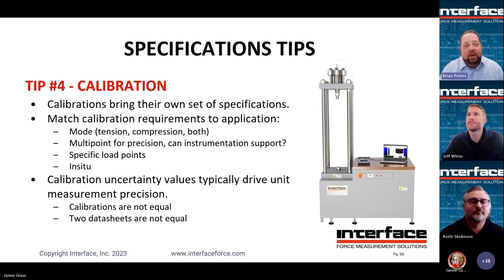If you're looking at the sensor specs, what kind of cal does it come with? Do you have a multi-point? Do you have a single point? And then the last part too: what is the uncertainty of the calibration? That's usually a separate question you need to ask. You can be looking at two data sheets side by side, but if one has a 0.04% or 0.02%, and it's a dead weight type cal versus an unknown or uncredited cal, it makes your measurement a little bit risky.